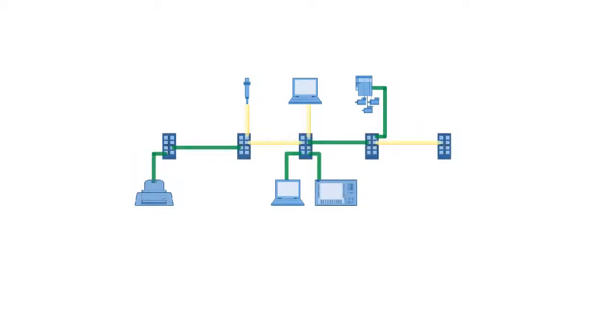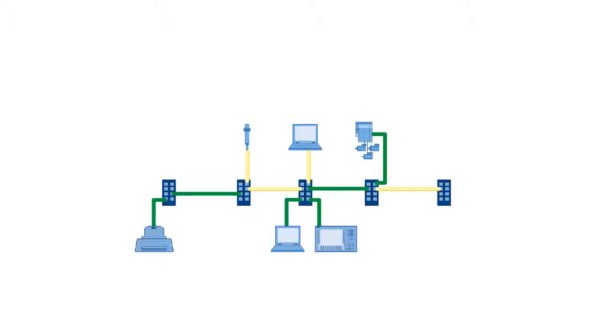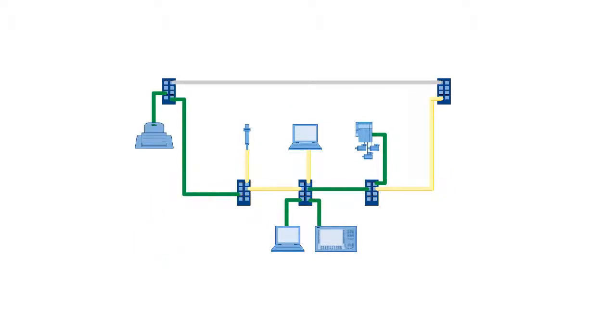For high-speed redundancy, we are looking at a network which, in its most simple configuration, consists of a line from which the individual end nodes branch off. Each node of the line is equipped with a switch suitable for high-speed redundancy. The network may consist of optical as well as electrical segments, depending on the available ports of the switches. For high-speed redundancy, the line is closed into a ring. One of the switches in the later ring is configured as the redundancy manager.